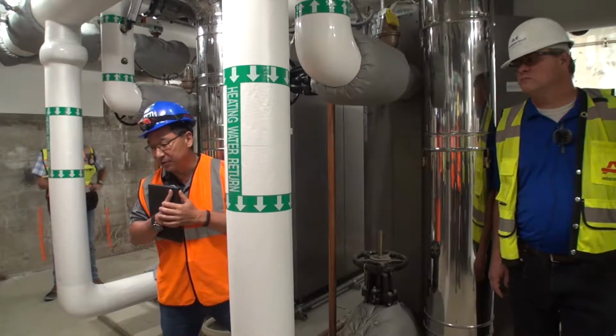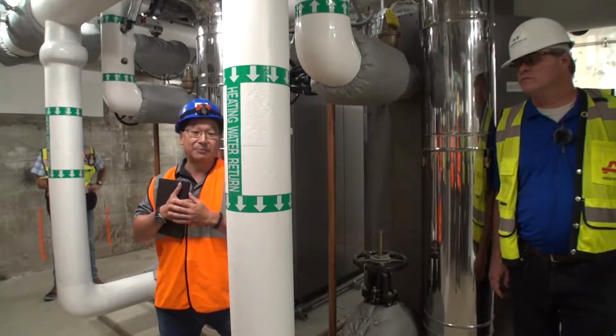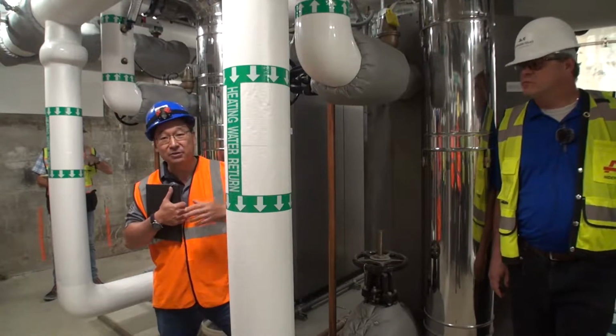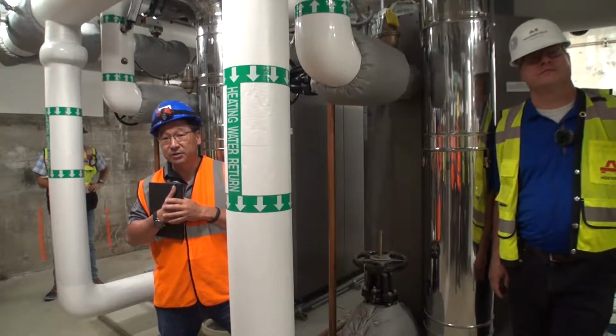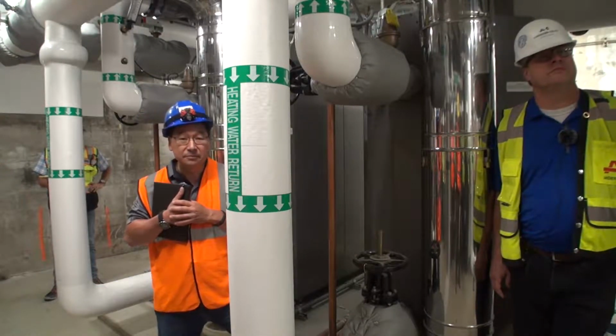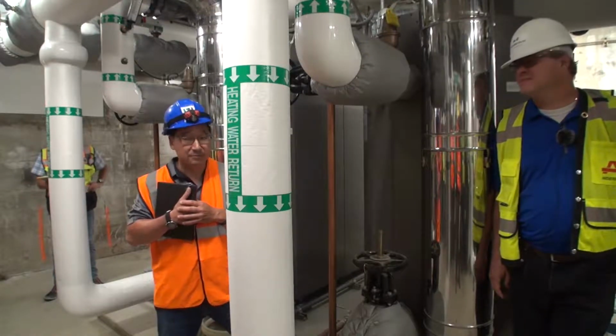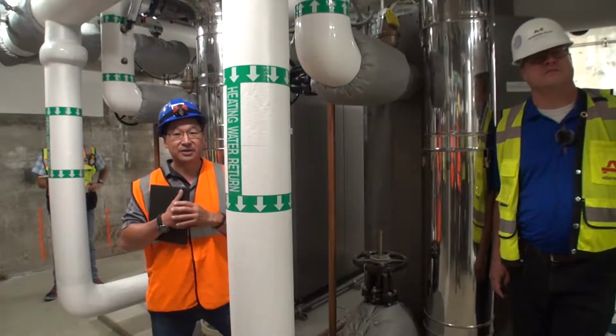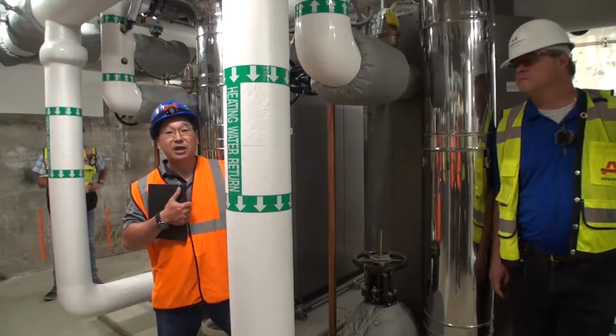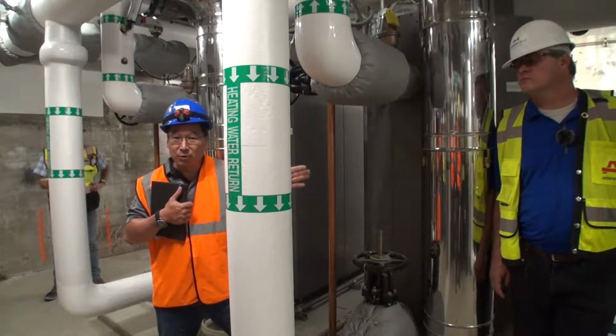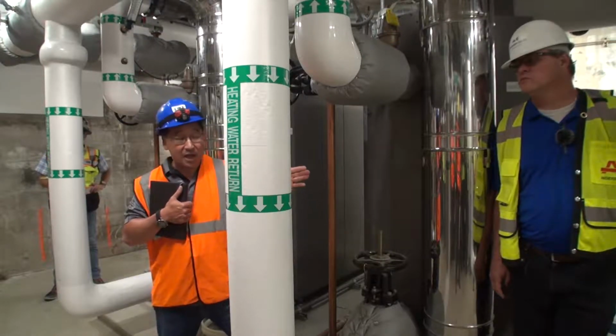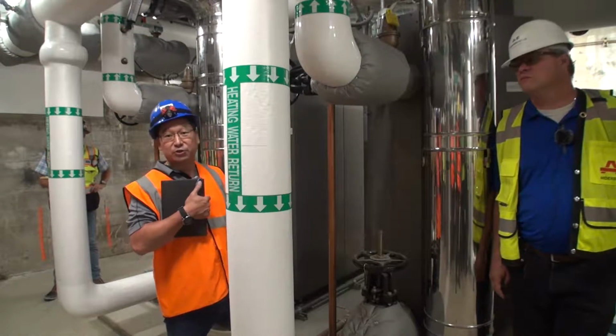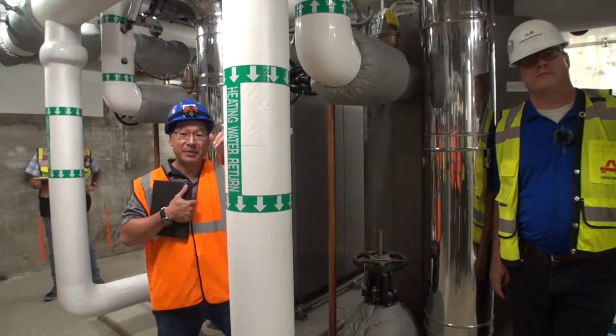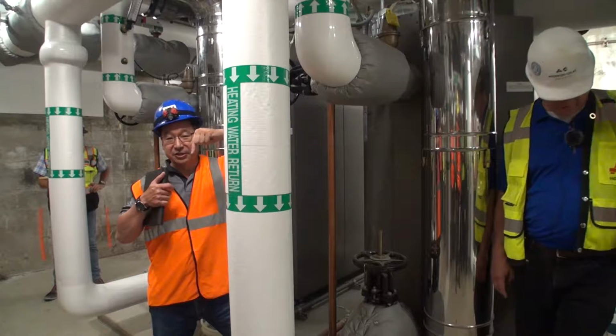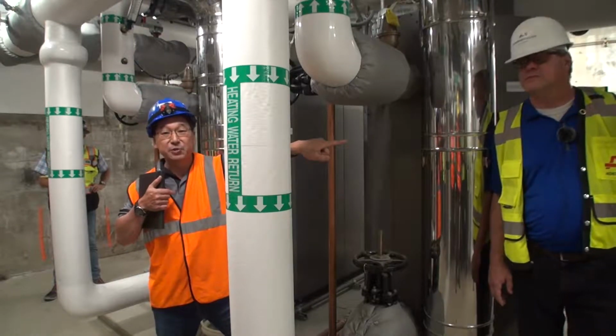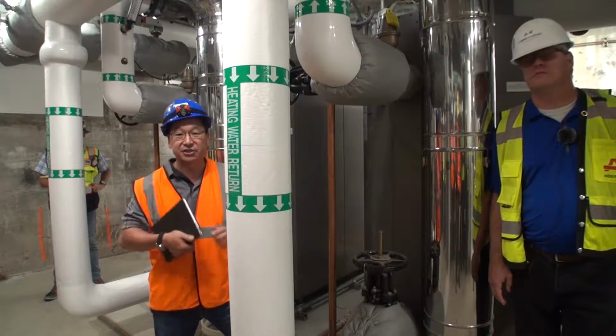If, for instance, it comes to maintenance and you have to operate the boiler without that one, give us a call. We can walk you through it. So we should probably put a label on it, never turn it off. Correct. Even if it's in fault, leave it on. Just leave it on, because it's the master. It won't be able to provide you heat if it's in the safety fault. However, it'll still command the other 2 what to do based on that temperature sensor that's in the main. There's a main sensor in the supply to the system. This boiler's reading it, and based on that temperature, it's making decisions.